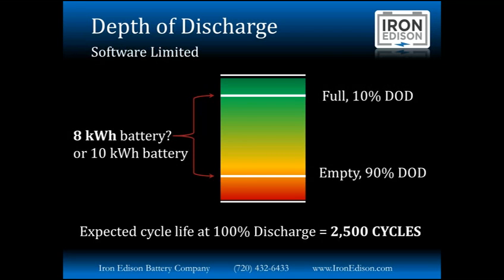So what we're seeing today is software limited depth of discharge. This makes it very hard to compare apples to apples between different types of lithium batteries from different manufacturers, because although the chemistry is the same, what each company is doing is using software to limit the total battery capacity. In this example, what we're seeing some of our competitors do is deliver a 10 kilowatt hour battery, but software limit its available capacity to 8 kilowatt hours, meaning that full is at 10% depth of discharge and empty is 90% depth of discharge, essentially giving you 80% of the full true battery capacity. Our competitors are then publishing specs that say expected life at 100% depth of discharge is 2,500 cycles, when in reality, what we're seeing is these 2,500 cycles would correlate to an 80% depth of discharge number.